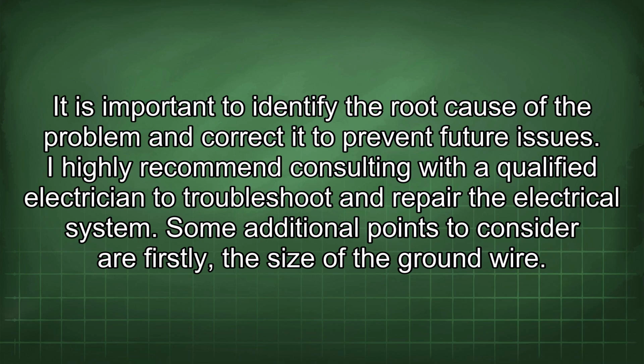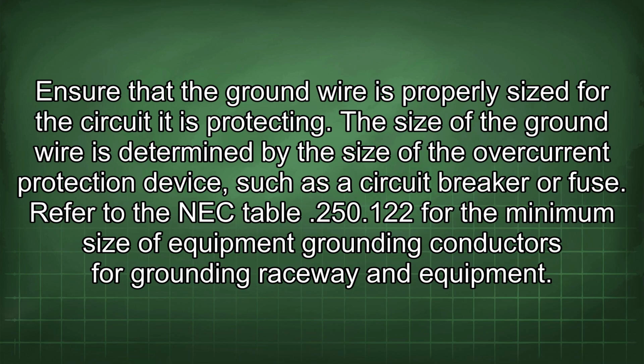Some additional points to consider are firstly the size of the ground wire. Ensure that the ground wire is properly sized for the circuit it is protecting. The size of the ground wire is determined by the size of the overcurrent protection device, such as a circuit breaker or fuse. Refer to the NEC table 250.122 for the minimum size of equipment grounding conductors for grounding raceway and equipment.